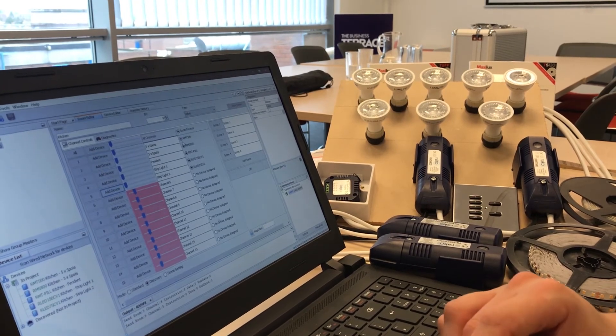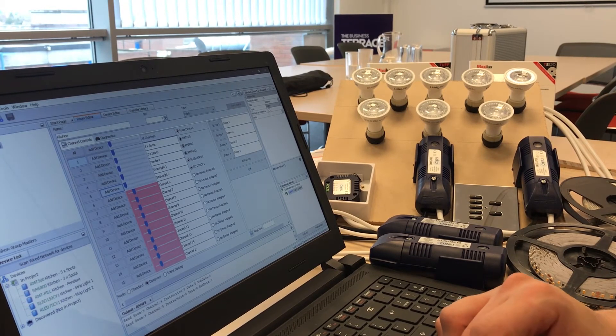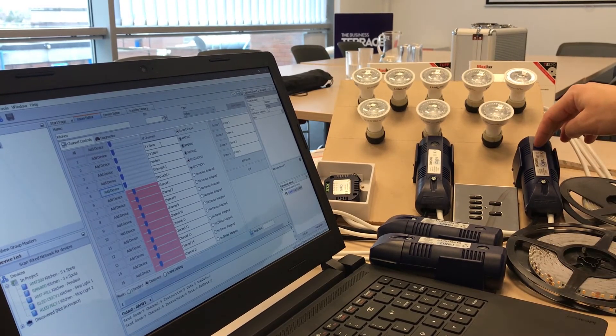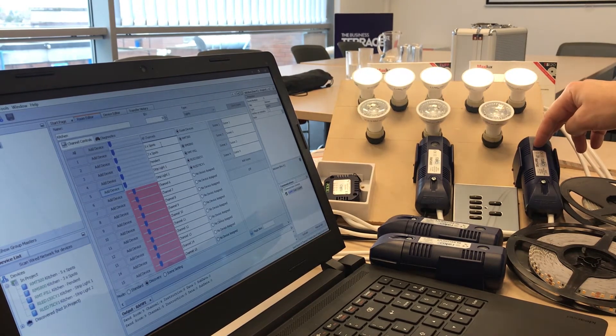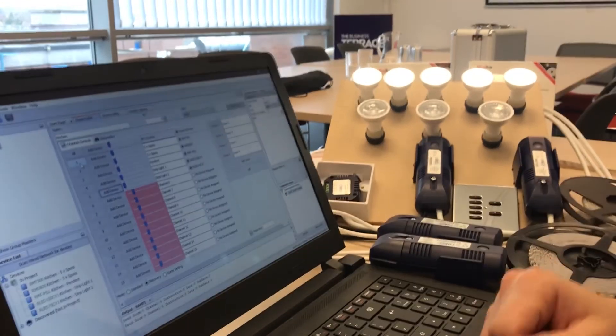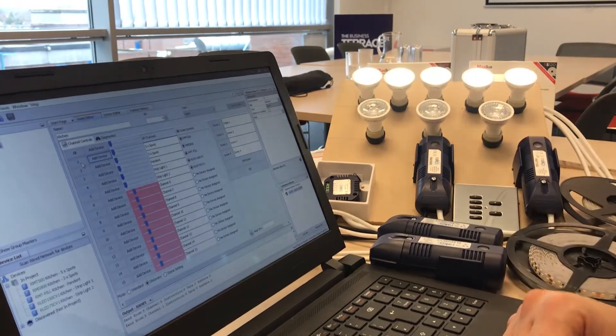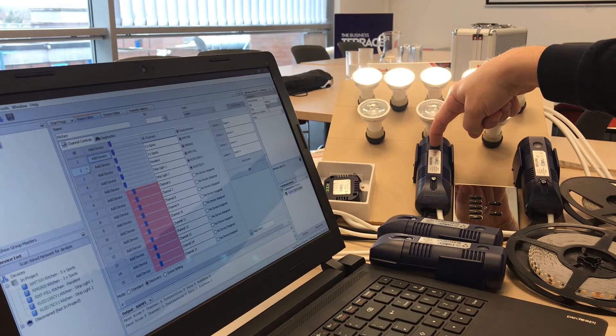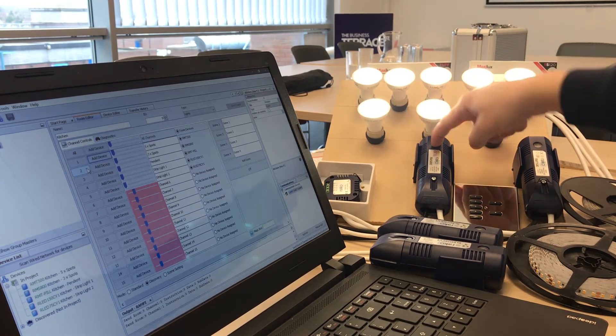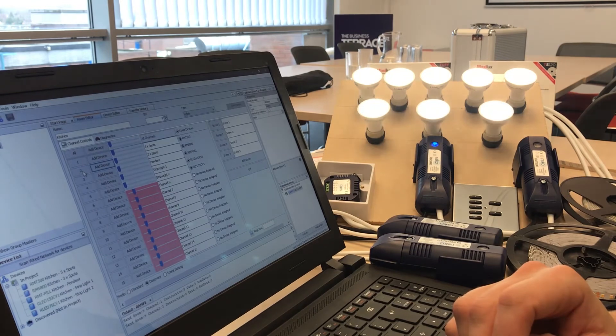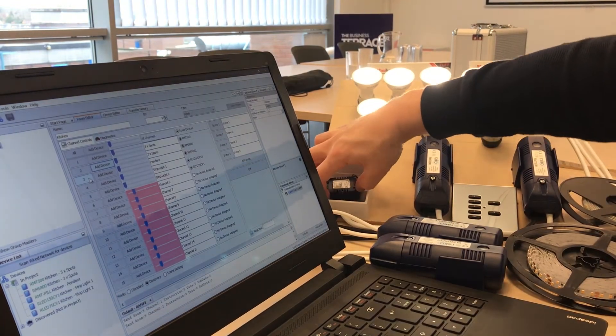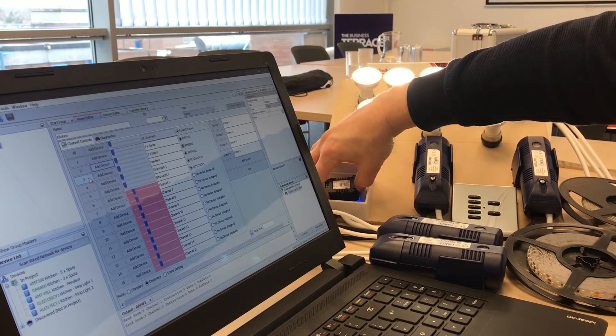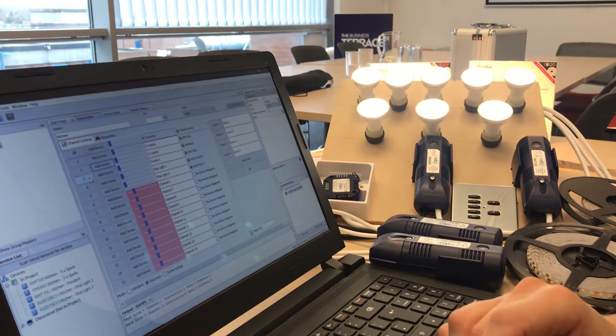Okay so that was a really quick and simple way of just naming the devices. And then what we're going to do is identify them. And again what we do here. So for our 5 spots we hold down our button. This puts the module into programming mode. So as you can see we've got a light flash. And now we've got the blue LED light flashing. And then on our software again we're just going to click circuit 1 to ident that to circuit 1. And again we're just going to go down our list. So we're going to hold button press this on the RMS 800. As you can see it's now going into programming mode. And then we're going to click on the relevant circuit back on our software. I'm going to carry on down the list here. So on the RM pill there's a little button on the side which we're going to hold down. There we go. We're into programming mode. And again we've got our ident.